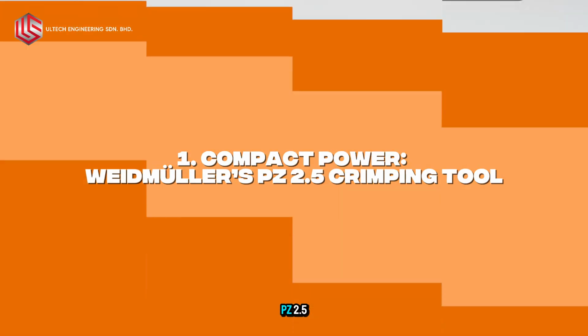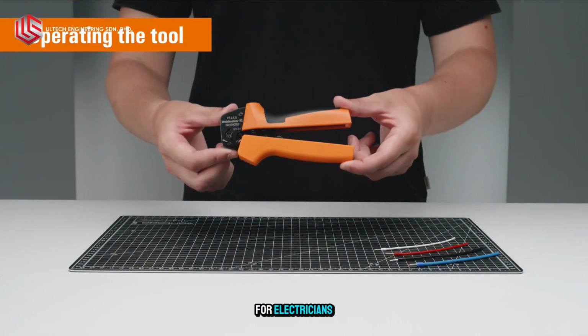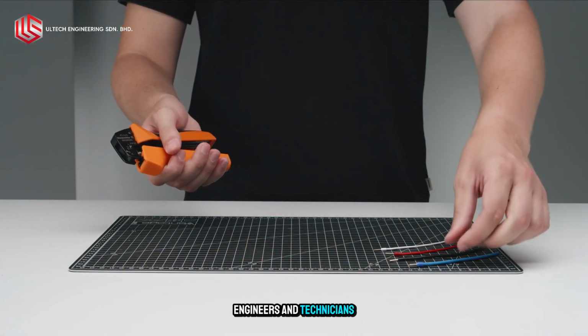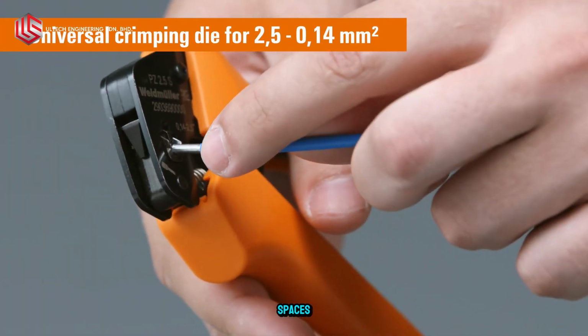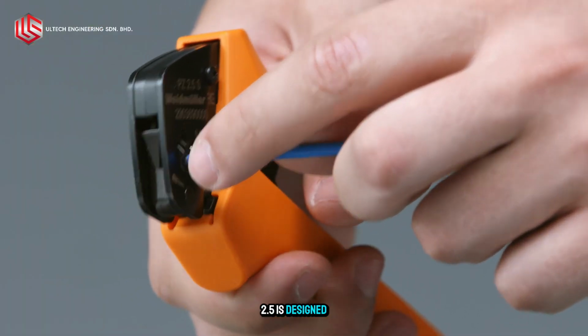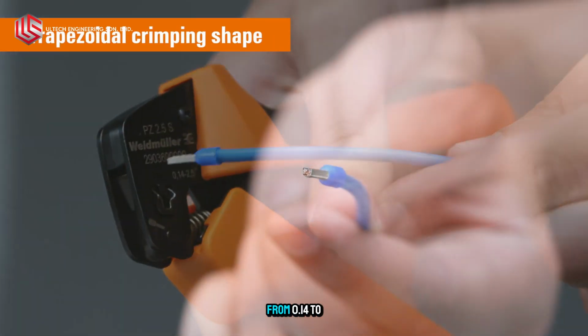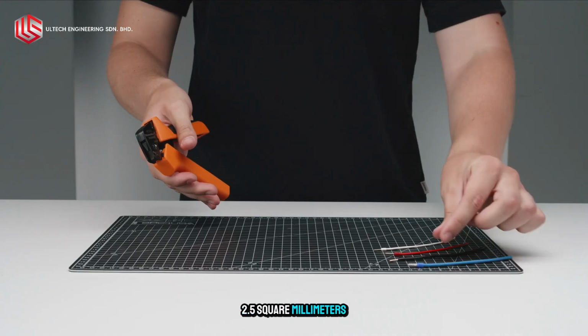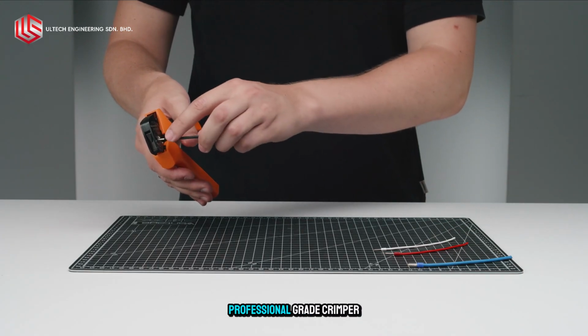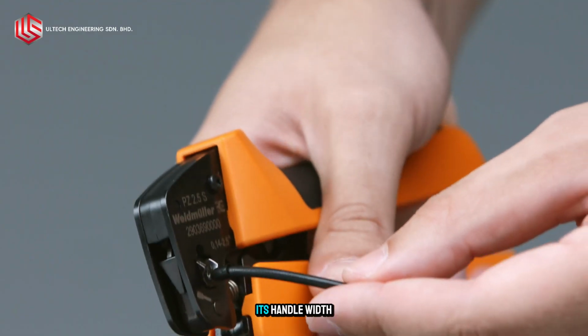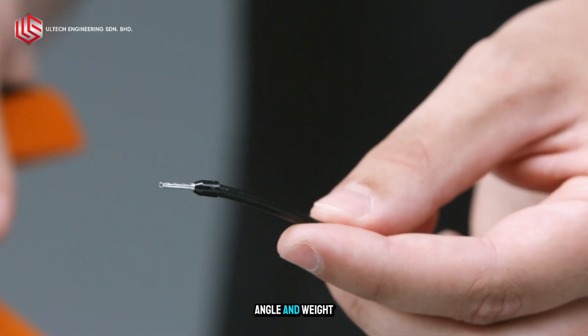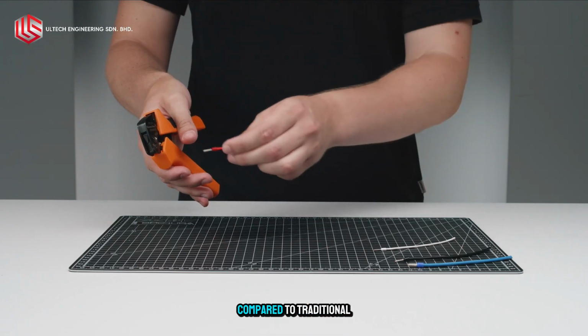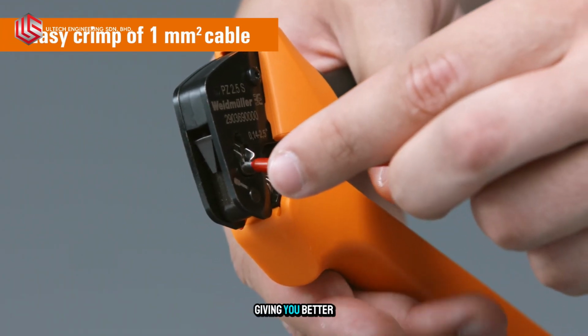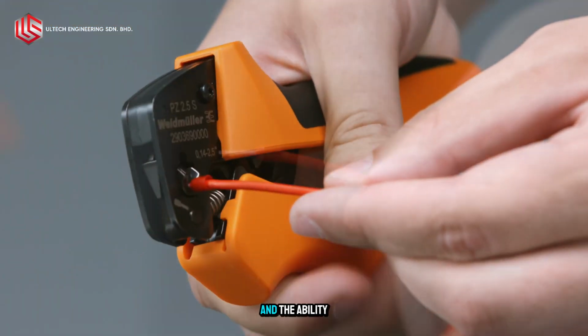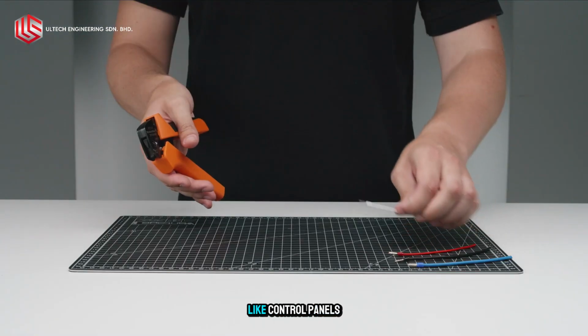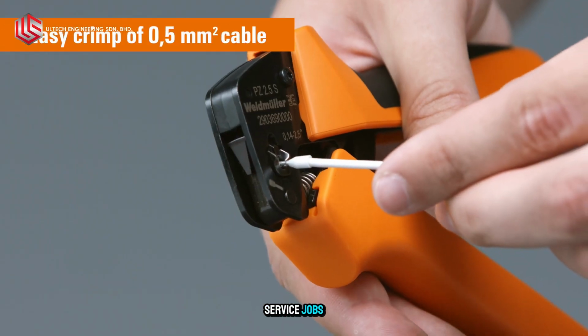Meet the Weidmüller PZ 2.5, a game changer for electricians, engineers, and technicians who need big performance in small spaces. The PZ 2.5 is designed specifically for wire-end ferrules from 0.14 to 2.5 square millimeters, making it the smallest professional-grade crimper in its class. Its handle width, jaw opening angle, and weight are all reduced by around 30% compared to traditional crimpers, giving you better control, less hand fatigue, and the ability to work comfortably in tight spaces like control panels or on-site service jobs.